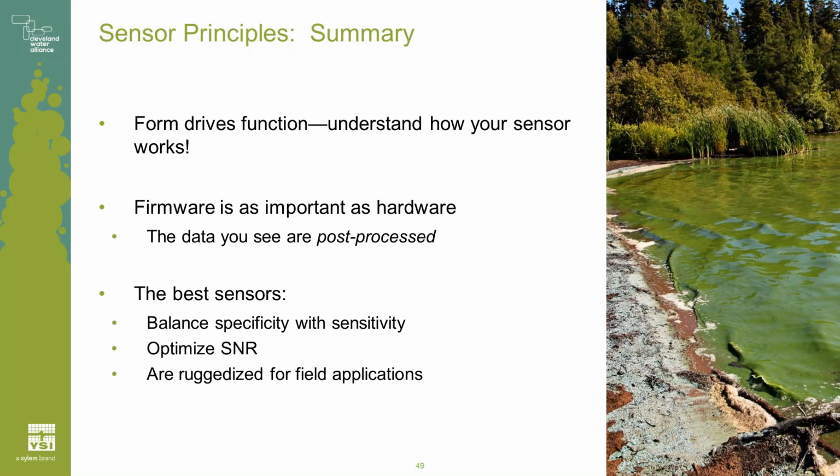The other thing that can happen, and what is more typical, Martin, with high turbidity, is a lower signal because light can't get back to the detector. So it really depends on what the nature of that turbidity is. If that turbidity has a lot of fluorescent material, it might give you an artificially positive signature. If that turbidity is a lot of sediment that blocks light passing through it and getting back to the detector, you get an artificially low signal. And definitely, again, old sensors and some of our competitor sensors that are only single channel sensors are far more prone to that.